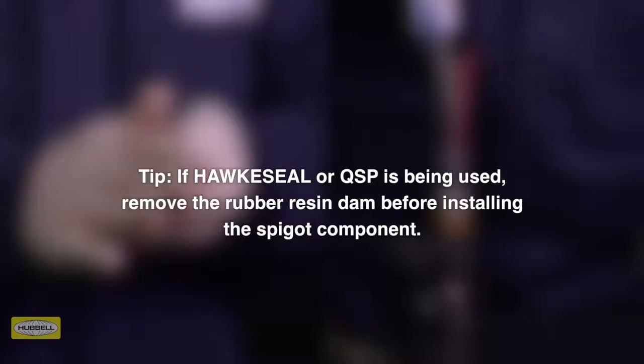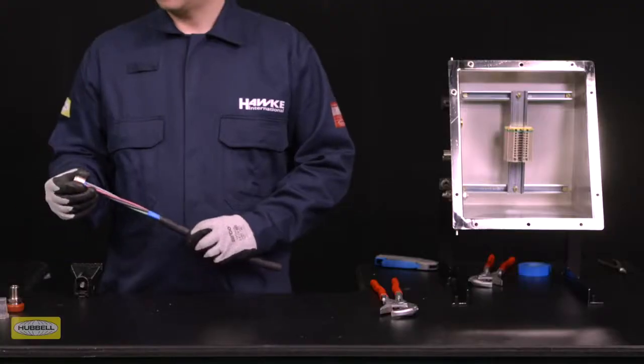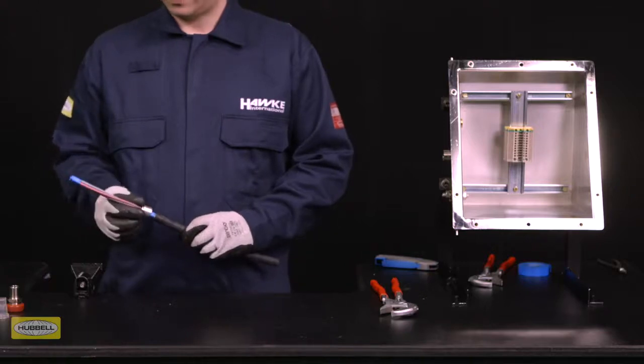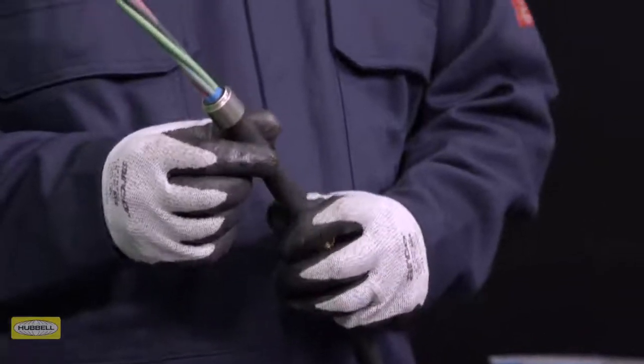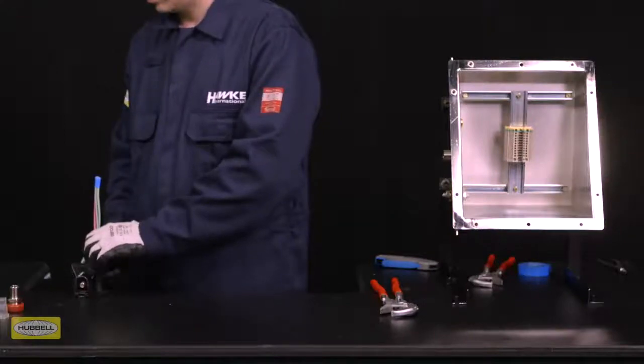If Hawk Seal or QSP is being used, remove the rubber resin dam before installing the spigot components. Slide the spigot over the cable, taking care not to damage the rubber resin dam, until the rear end of the spigot is at the point where the inner sheath is stripped back. Fit the pot and check that the inner sheath is at the height of the pot shoulder.